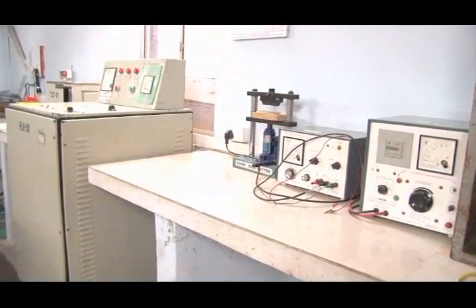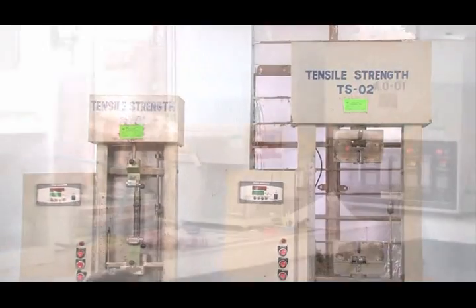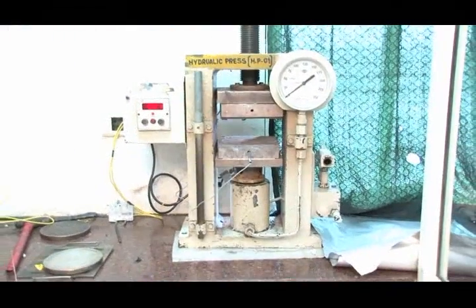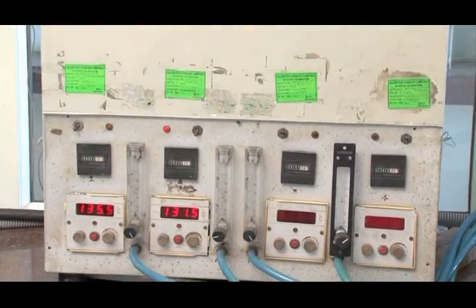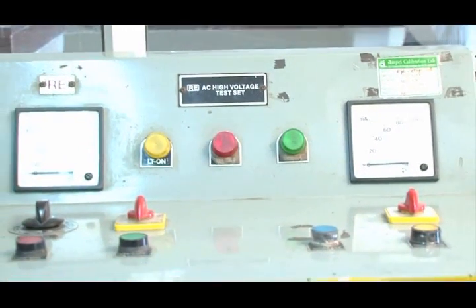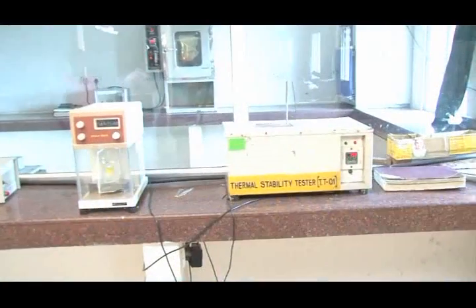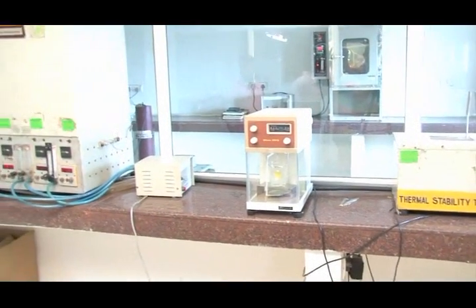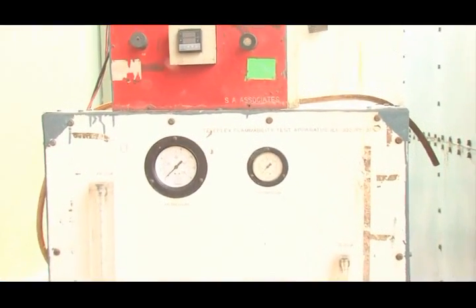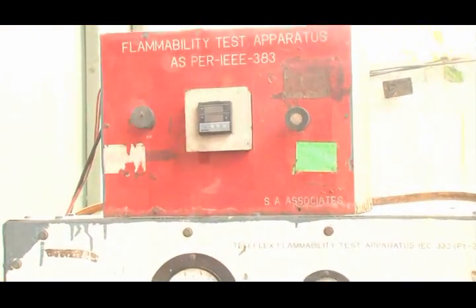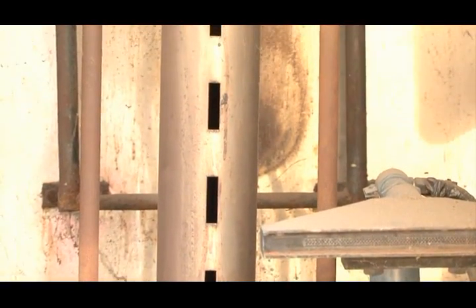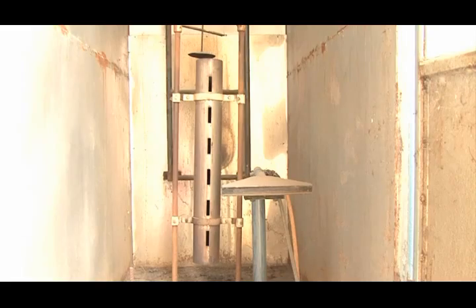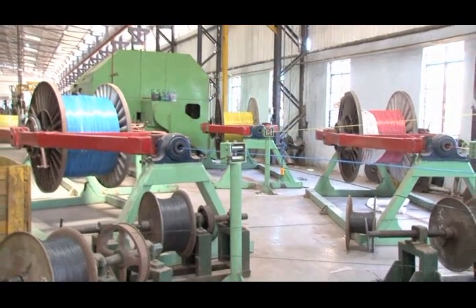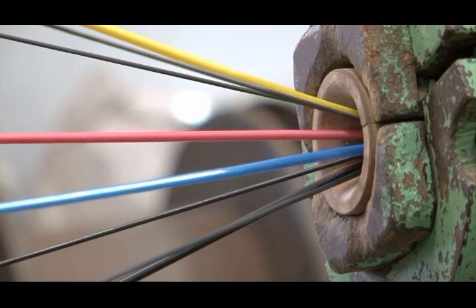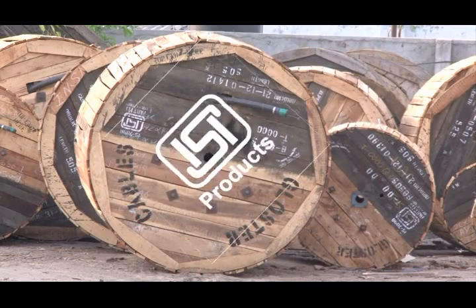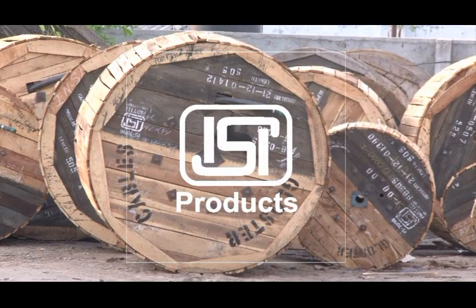In order to ensure quality, low voltage cables will have to pass through a series of tests, namely routine tests, type tests and acceptance tests. Conductor resistance test and high voltage tests are known as routine tests. Type tests are carried out on samples drawn from every production lot to check whether all parameters are in conformity with IS specifications. Acceptance tests are conducted in the presence of the external inspecting authorities to get their approval. We produce our low voltage cables with PVC and cross-linked polyethylene insulations. All the cables produced by Gloster have ISI certifications.